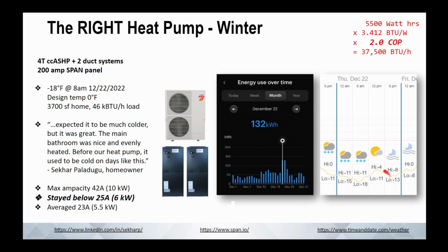And this is the weather data over here. Here's our low of -18. And it wasn't that cold all day, of course. It got to a high of -4, right? So there's averages involved there. But we're still operating 200% efficient. I would say that's pretty good. And it's definitely better than what the specs say. The specs would say you're pumping 10 kW into this thing at 0 degrees. And we're beating that, right?